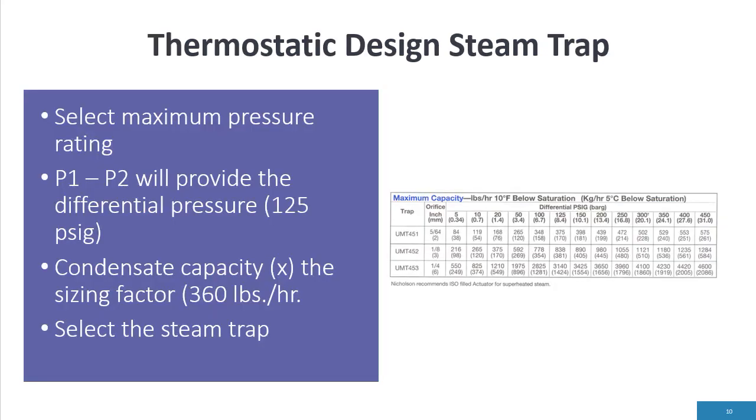If I come down to my sizing chart, the maximum pressure rating we said was 150 psi. All these steam traps here have a maximum pressure of 450 psi, so it's not as prevalent in the mechanical design steam traps. I come here to 125 psi differential, find something greater than 360 pounds per hour. I see I have a steam trap here, 838 pounds per hour, so it'd be a model 452. And then I made my selection of my steam trap.